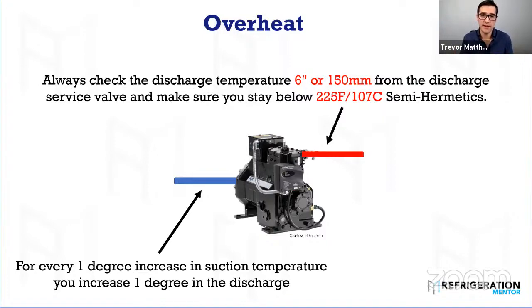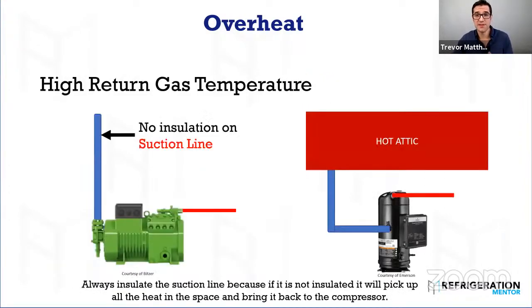And any temperature increase in your suction is the same increase in your discharge. So if you have suction gas coming back hot, you don't insulate your suction line, or you have insulation that's really old, like 10 or 15 years old, and it's going through a hot attic or a hot space, even though you have insulation, if it's bad insulation, all that heat could be coming back to the compressor and causing damage, overheating the compressor, causing it to fail.